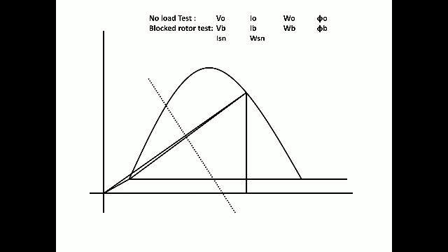So this is the thing. Now you need to segregate the copper losses. Now we have two portions here, which means stator copper loss as well as rotor copper loss. It is separated by the torque line. There is a separate equation for the torque line calculation for the slip ring as well as the squirrel cage. If the data are there, we can proceed on that scenario, or else we can make it a 50-50 portion. So make this 50-50 and draw a line. This line is called the torque line. So that's all for the basic data.